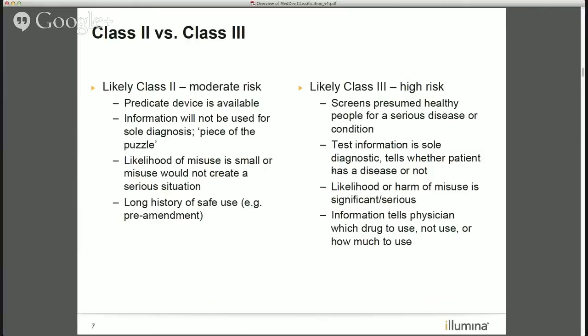Relative to misuse of your device, if the chance of misuse is small or the misuse wouldn't create a serious situation, you're likely going to be Class 2. Conversely, if there's a high chance of misuse that could lead to significant injuries, you're likely Class 3. Devices with a long history of safe use on the market are demonstrated at moderate risk. And the latest trend — personalized medicine and companion diagnostics — where information tells a physician which drug to use, how much to use, or whether to use it at all, those currently fall into the Class 3 high-risk category.